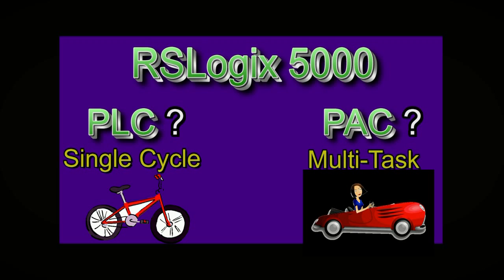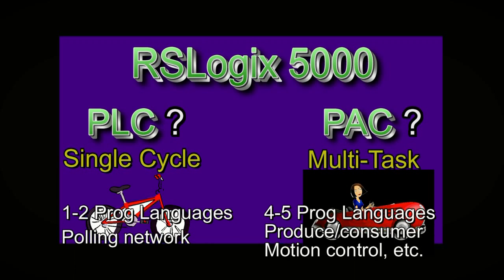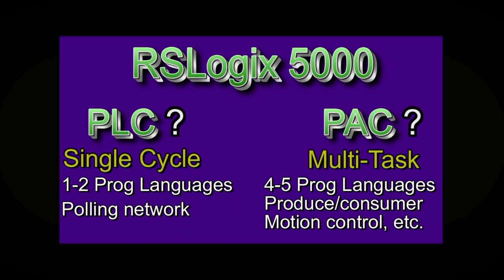A PLC typically has one to two programming languages; a PAC has four to five. A PLC is restricted to polling a network and backplane in between scan cycles. With a PAC, every module is a device on the Ethernet network.